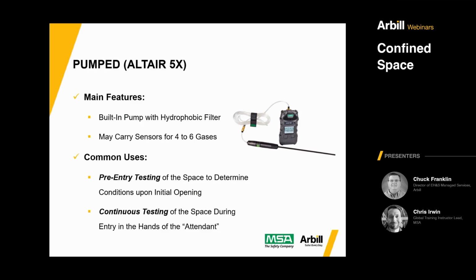This gives you another view of what I said previously. So the Altair 5X—you can see there's a pump and filters built in. We can't see either filter from this side, but on the back, right where it plugs in, there's a hydrophobic filter, and in the wand, the plastic black piece at the end of the tubing, there's also a hydrophobic filter in there.